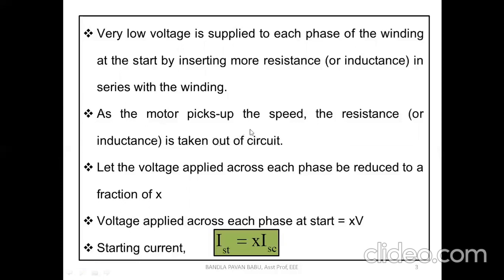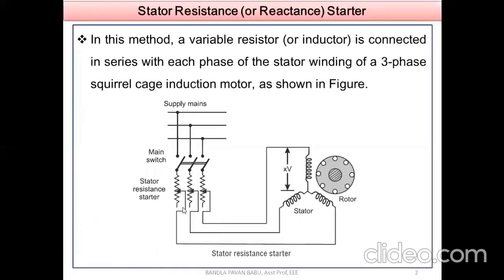So what happens, we'll see. As the motor picks up the speed, the resistance is taken out of the circuit. So initially we are regulating the voltage, that means a low voltage, maybe 20% or 30% or 50%. So slowly, at the starting itself, we are applying a low voltage. Soon after, as it is trying to reach the rated speed, gradually we are going to remove the resistance. Removing the resistance means either we can bring it back to the minimum position, or we can remove the total resistance by the help of additional switches.